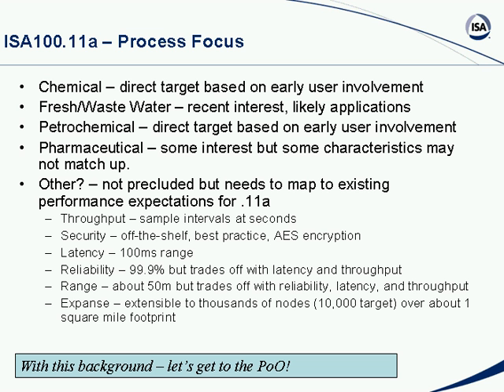The performance expectations for DOT 11A, based on current thinking in the committee: throughput will support sample intervals on the order of seconds; security will be best-practice off-the-shelf incorporating AES — American Encryption Standard — encryption; latency will be on the order of 100 milliseconds; reliability will be what's called three nines. We see a range of about 50 meters, but you may trade that off with reliability, latency, and throughput depending on how you configure your network. We expect DOT 11A to cover thousands of nodes — up to about 10,000 nodes — over about one square mile footprint.